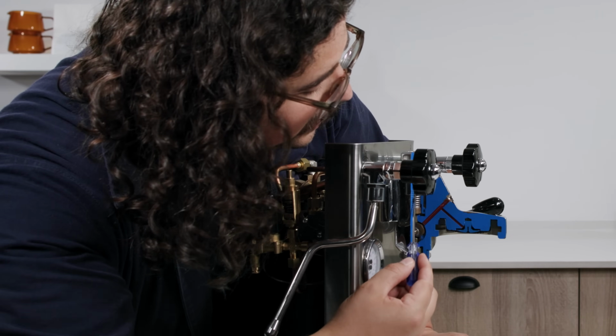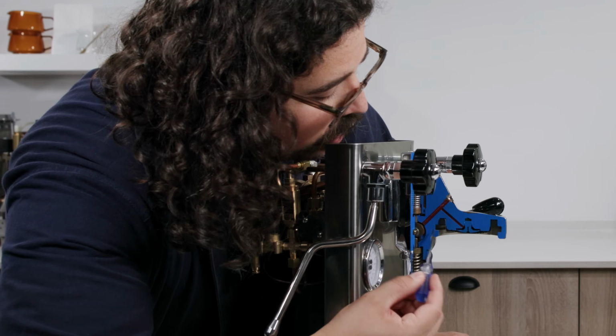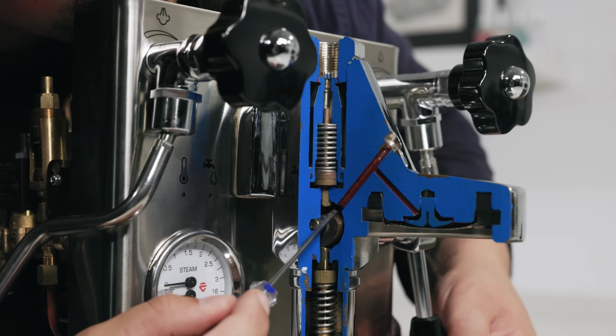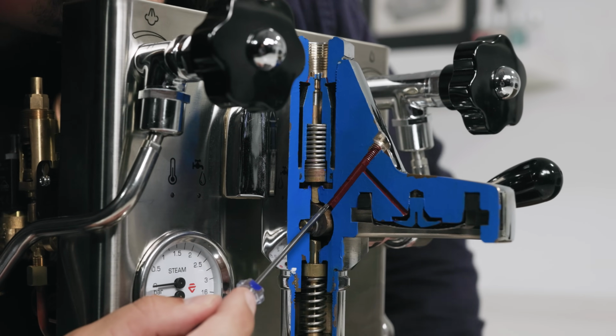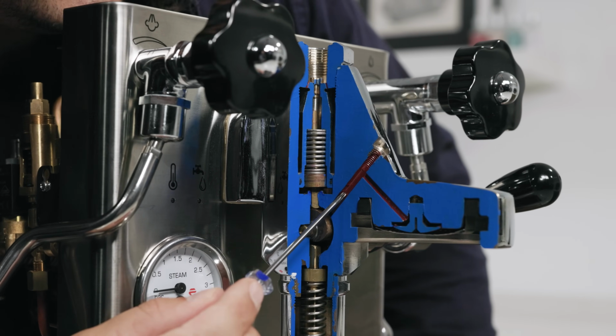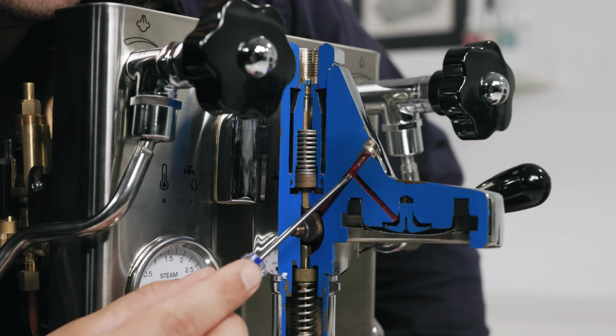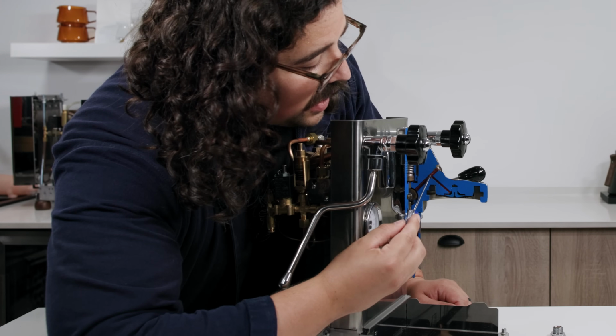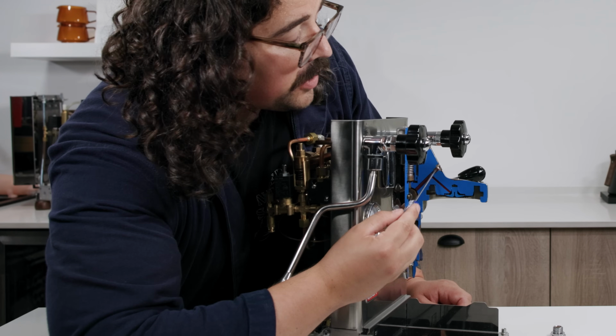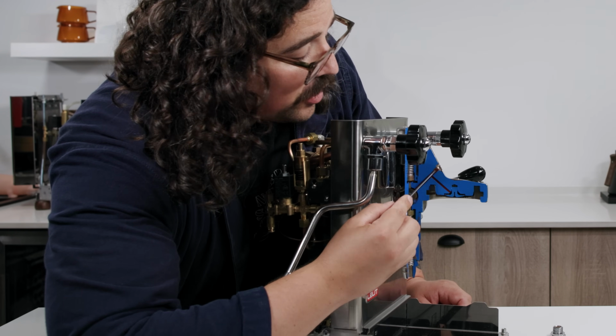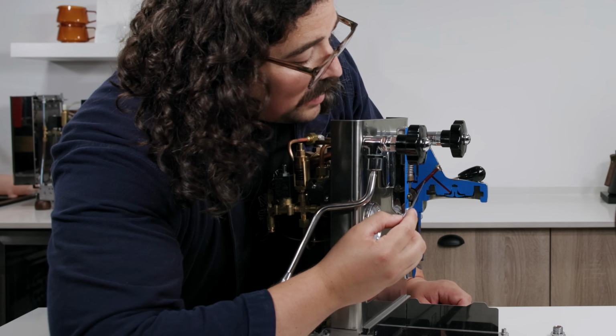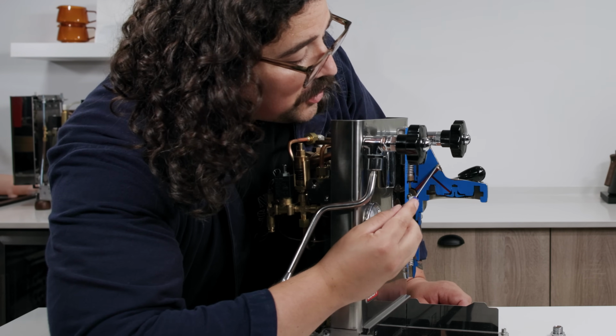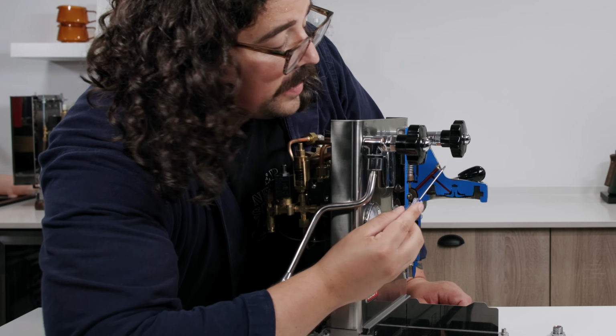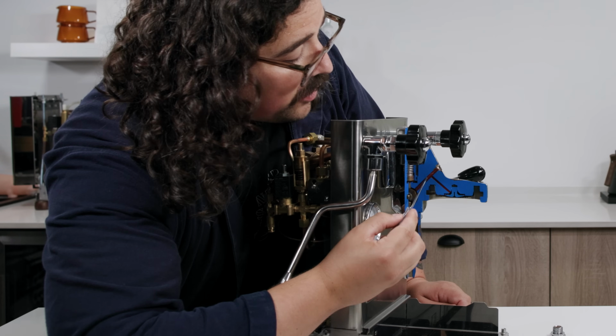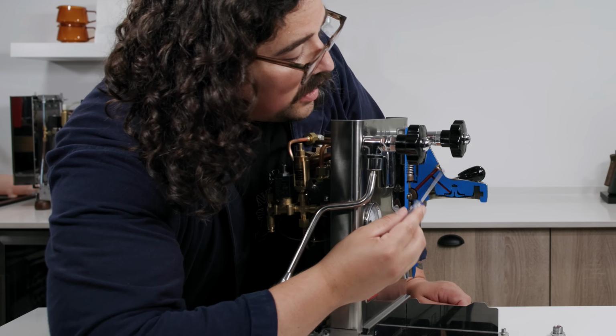So the water's coming down here, and since that valve is now open, see, when it's here, it's closed off. Now that it's open, it can travel around here, and then it enters into the group itself, into the actual head. So the water comes up, it says hello to the pressure gauge or whatever you have here, or if you have a thermocouple in here, it's able to read the temperature there. But regardless, it pushes pressure here. You can have a screw here, a pressure gauge, a thermocouple, whatever it is, or both, with a Y splitter.